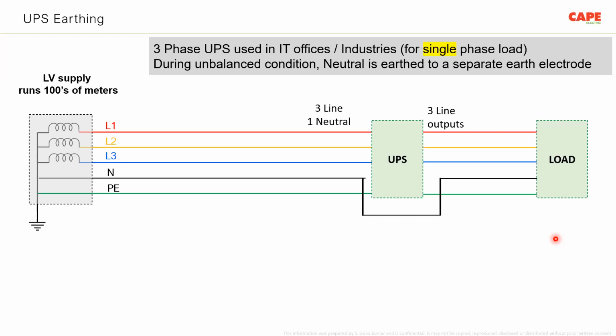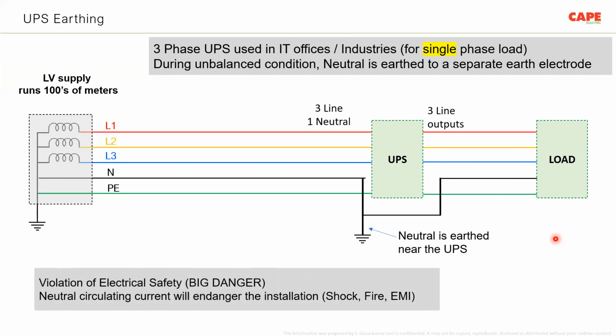Now, engineers found a solution, and this solution is more interesting to understand. This neutral near the UPS, they take a wire or a bus bar and run it probably 50-60 meters and connect it to an earth pit in soil. And they say that this is the neutral earthing of the UPS, or the neutral conductor which is running inside your installation. At some point, some place, it is taken out and connected to an earth pit in soil. And this earth pit is always isolated from the other earth electrodes. That means it is separate from the earth electrodes. So if you connect this to the earth electrode, something happens. This is what people think.